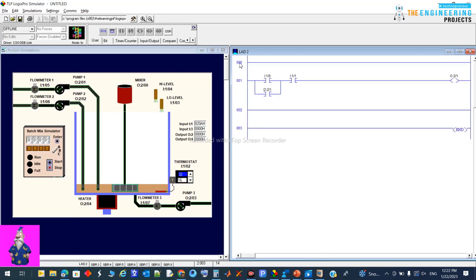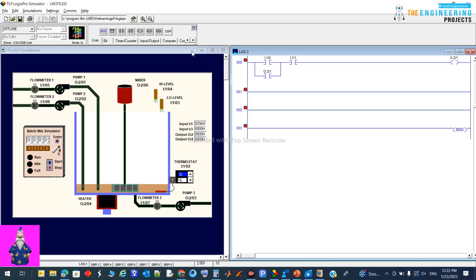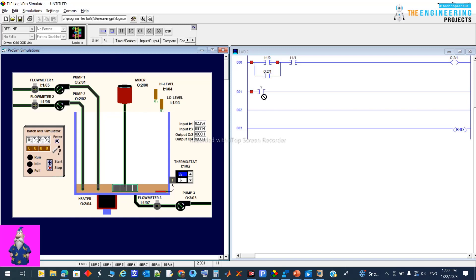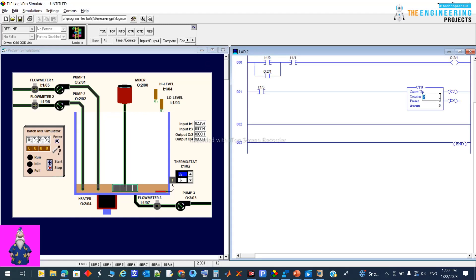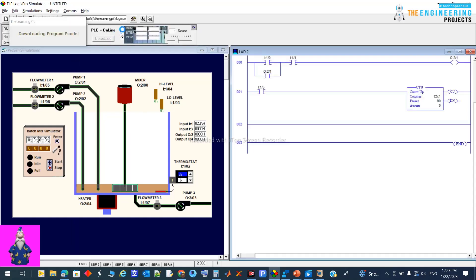This will be my first rung. In my second rung, I'll add the flow meter — so the flow meter showing the pulses for the filling. I need one counter, so going to the counter, I need a count-up. I will have this as C51. This is my counter, and they say at 90% — I don't know the count value yet, so let's check the count to see how it's counting.